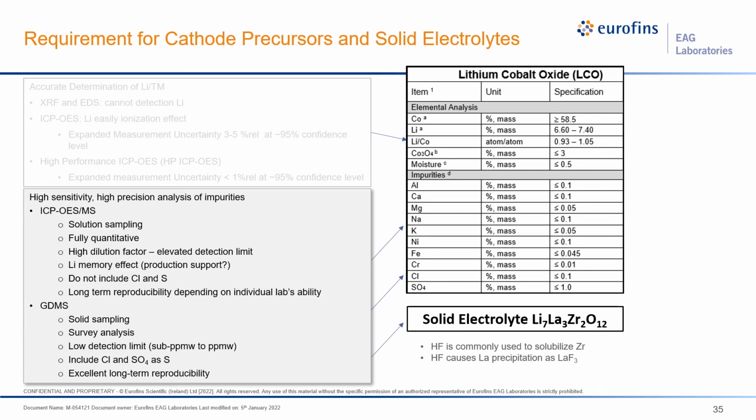Well, HF is known to precipitate rare earths pretty easily as a rare earth oxide fluoride. For example, lanthanum has an extremely low solubility product, so any addition of fluorine has to be very carefully controlled, otherwise the entire lanthanum will precipitate out. As such, it is a very cumbersome process to do impurity analysis with the ICP technique for those materials. Rather, GDMS will be our natural choice.